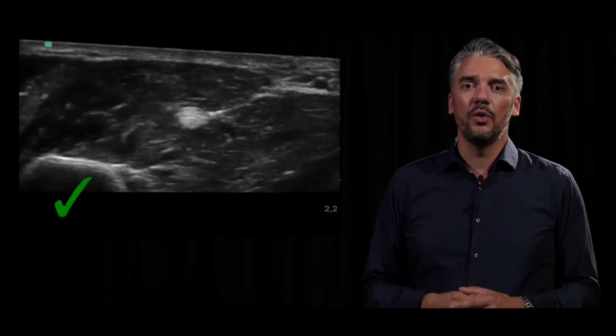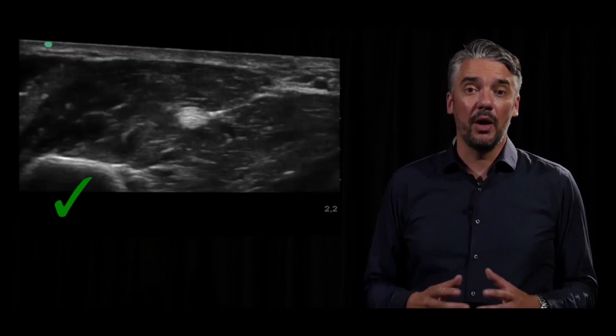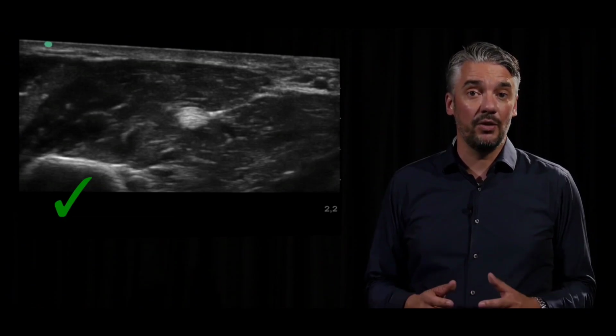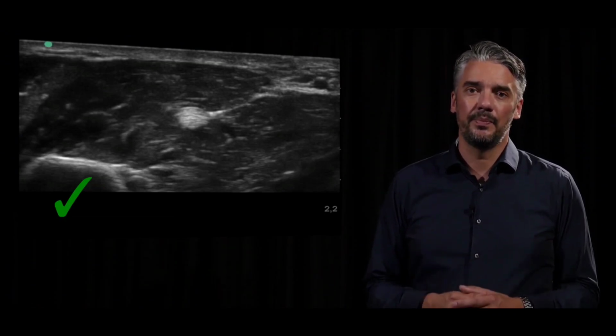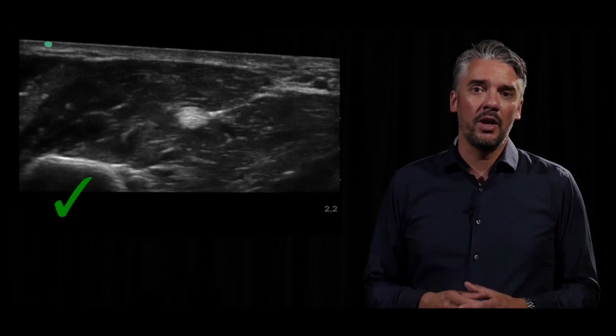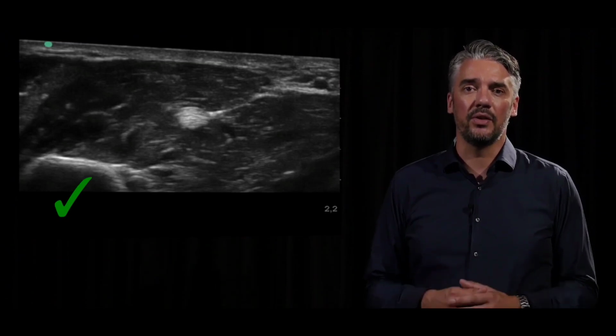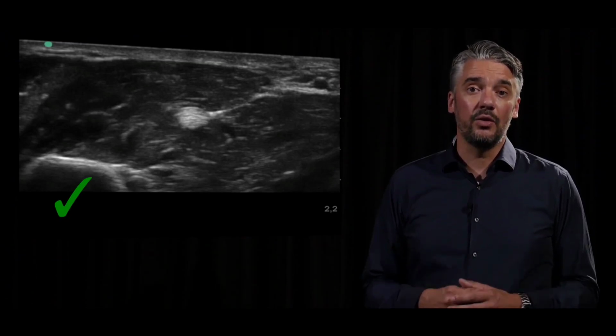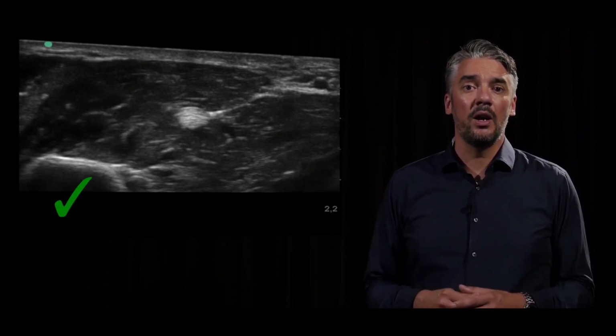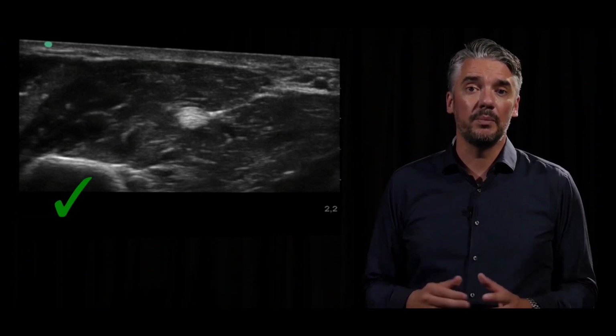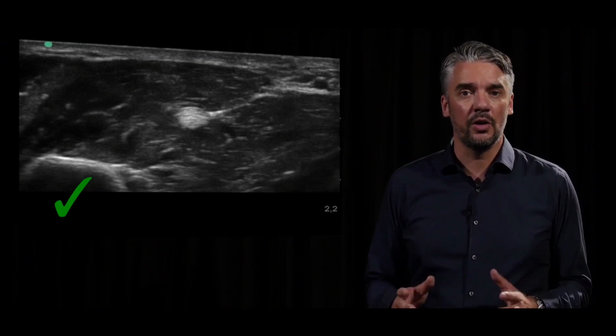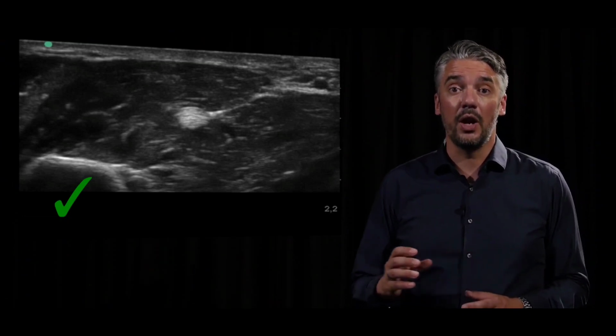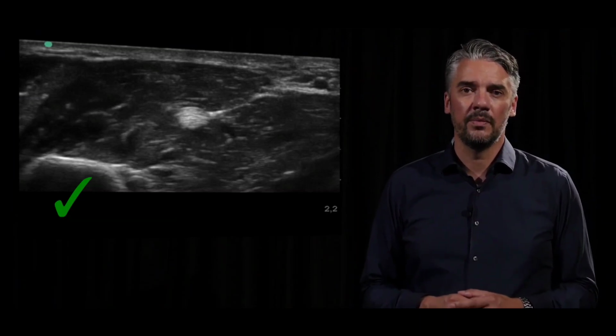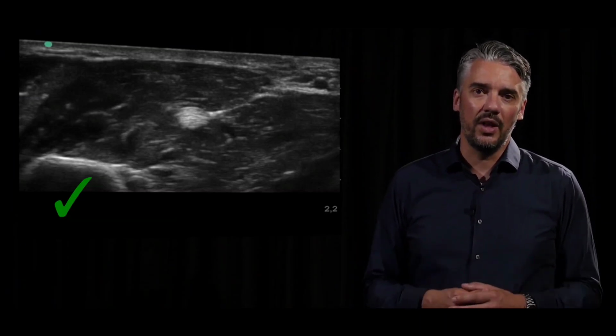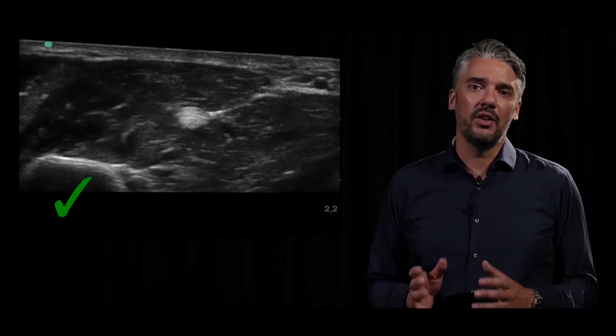This image shows much more detail and brightness due to the application of gel on the transducer. Always make sure that there is plenty of gel present. It not only serves to prevent the interference of air, but also enhances the gliding possibilities of the transducer when sweeping the transducer around the region of interest. As soon as the gel dries up, please add additional gel again.